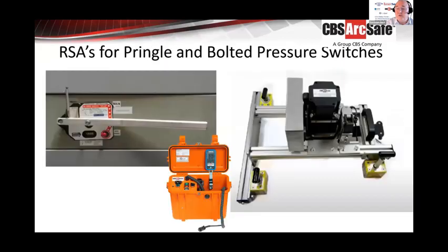The first question was, how do you make sure that the racking mechanism will stop the breaker in the correct position? Okay. So first, there are video options available. If you want to stop the breaker, let's say in the test position, you can watch that position indicator and just let go of the control when you get to that point. And that's for our application specific devices.